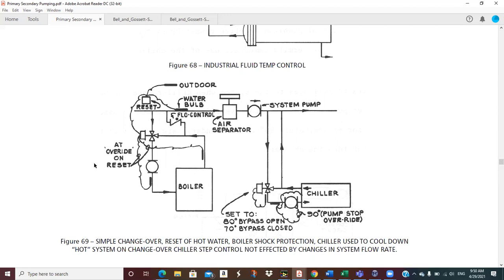But here's your system pump that's circulating. And then I've got a separate little circulating pump on my chiller to pull cold water out of the chiller, which then can go up here to the system. And then I can get some warm water from the system and put it back through my chiller, and a similar kind of arrangement over here on the boiler where it's got its own. And, you know, I can do reset.